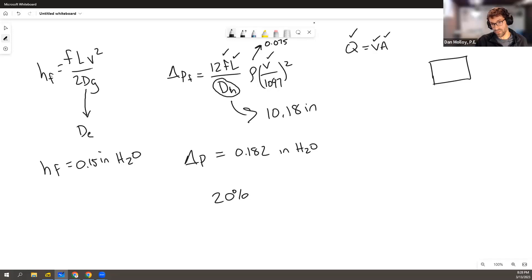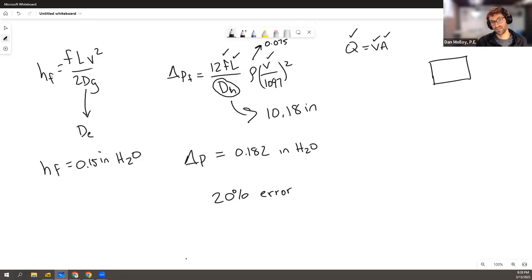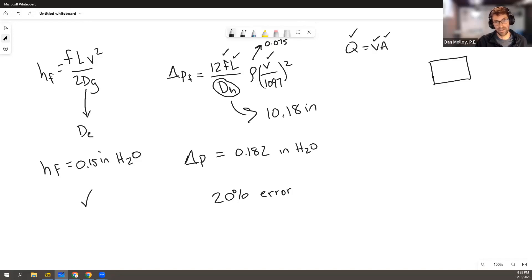So which is right? And I guess it comes down to should you use DE or should you use DH? My argument is that it's a duct, so you should use the diameter for rectangular duct. So I'm kind of sticking with option A. I don't think it's quite true to refer to this as a conduit.